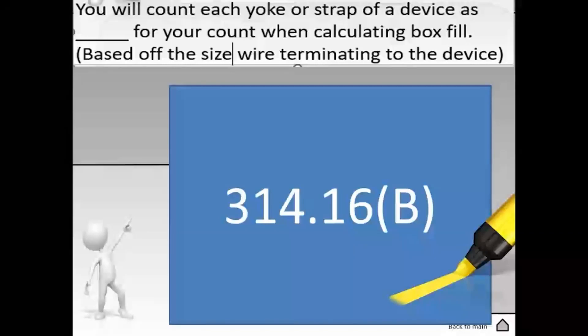Then a few more lines down, I want you to highlight the words based off the largest conductor connected to the device. And then of course, go back up to part four and highlight the heading. So your highlighting will read device or equipment fill, each yoke or strap, double volume based off the largest conductor that's terminated to the device.